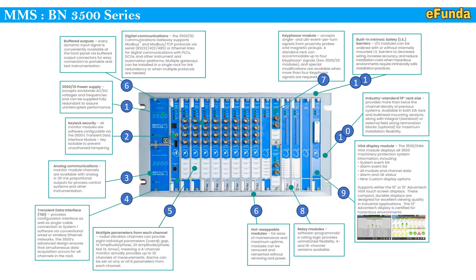Sixth — hot swappable modules for ease of maintenance and maximum uptime: modules can be removed and reinserted without removing rack power. Seventh — keyphasor module: accepts single and multi-event per turn signals from proximity probes and magnetic pickups. A standard rack can accommodate up to 4 key phaser signals via 3500/25 modules; special modifications are available when more than 4 key phaser signals are required.